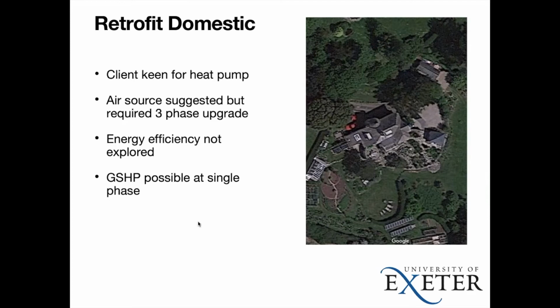When we looked at the building, relatively simple calculations showed that improving a couple of the windows and some insulation on a part of the house that wasn't insulated makes it completely viable to do it on single phase, particularly with a ground source heat pump. So this contractor really was losing out on the business, thinking, oh, we'll just put a big one in and hope they can afford it. But they lost the sale on that. So if we're going to help the sector move forward, highlighting things like energy efficiency, those sort of opportunities, and the whole system design, not oversizing, is absolutely critical.